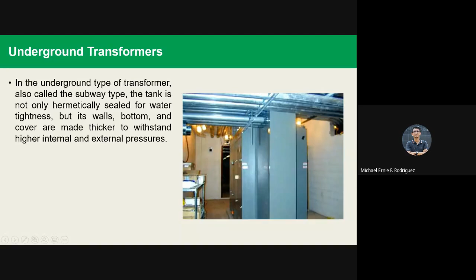So the cover is bolted to the tank with intervening gaskets, by a relatively large number of bolts, and in some instances welding is used. So these units are designed to operate completely submerged in water, of course, in case of flooding. So they'll still operate even submerged in water. So those are the different installations of transformers: overhead transformers, pad-mounted transformers, and underground transformers.